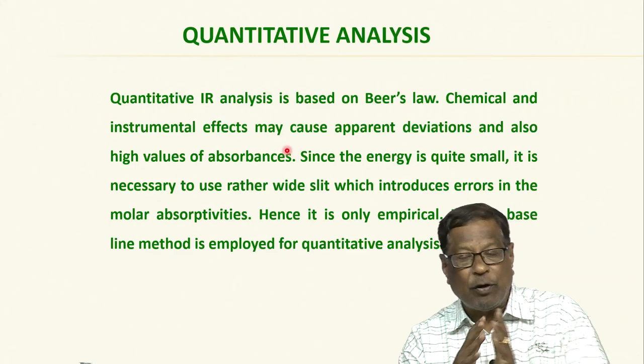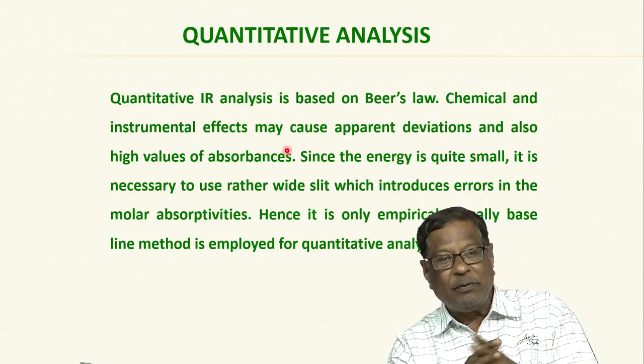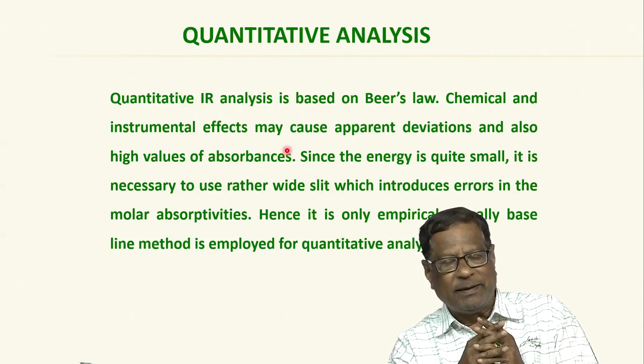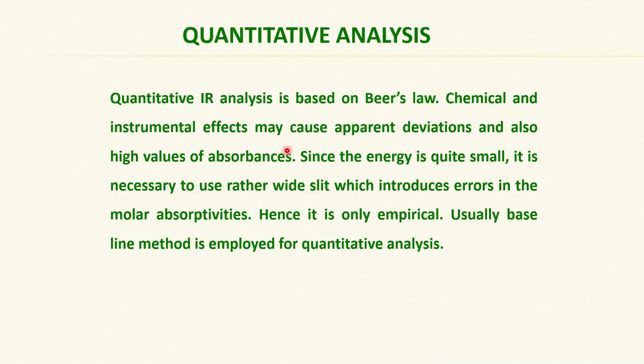This is one type of quantitative analysis we use in process instruments. If you want to do quantitative analysis of infrared for a given specific system in the laboratory, it is just like what we do in a spectrophotometer. Quantitative IR analysis is based on Beer-Lambert's law. Chemical and instrumental effects may cause apparent deviation.